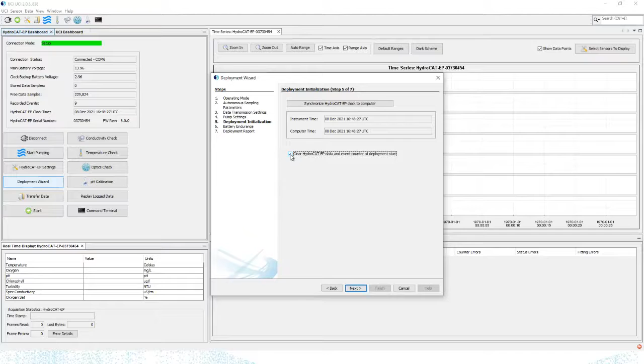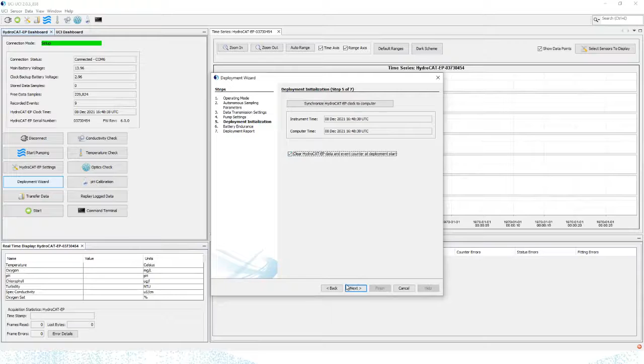Also, if you want to start fresh, you want to delete all the samples currently on the memory, make the entire memory available for this deployment, and also delete the event counter. If something happened, like a lost power, it will write a note into the event counter. If you want to start fresh, you can click on this, and it will delete everything currently written into the event counter, so you know any errors that pop up are new errors for this deployment. That helps with troubleshooting. When you do that, this little window will say, by the way, you're deleting all the data on your memory, make sure that's actually what you want to do before you proceed. So say yes.